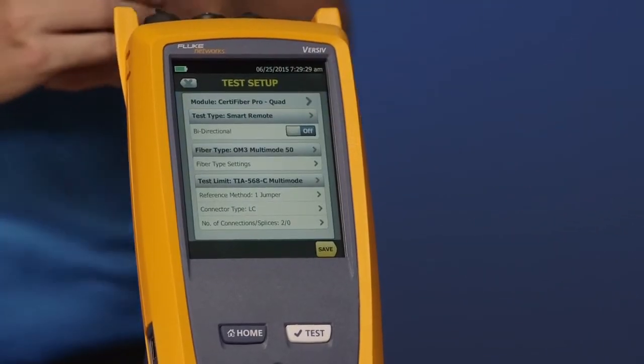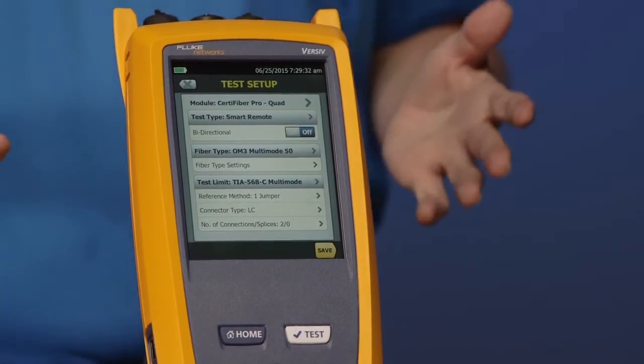We're going to leave it in Smart Remote. So Amanda, tap Smart Remote for me. That's fantastic. Looking down on the next option here, we have bi-directional. Now this can be an emotive decision. What I would say here is, look at your test specification. If your test specification calls out bi-directional, turn this on. Just be aware that none of the cabling standards in ISO or TIA require bi-directional testing. But your vendor may or your consultant may. So always look to your test specification.